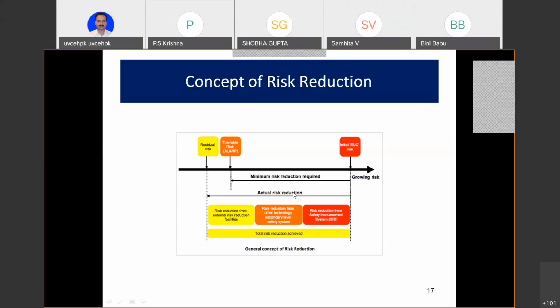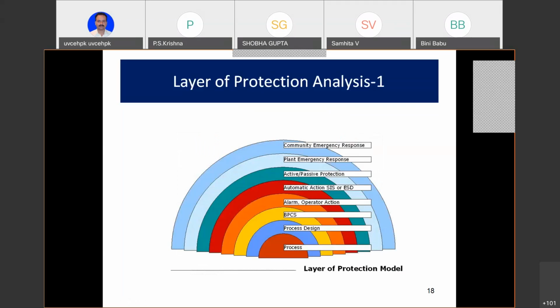So you're all now familiar with risk reduction. We talk about that hypothetical plant every time. Keep that in mind so that it becomes easy to follow. This is what Shrikant had told you yesterday, and I'm not explaining it further because in principle it doesn't depend only on the safety instrumented system. There is a relief valve system, and then after that you can contain the explosion. Sorry, the gas removal. That is done.